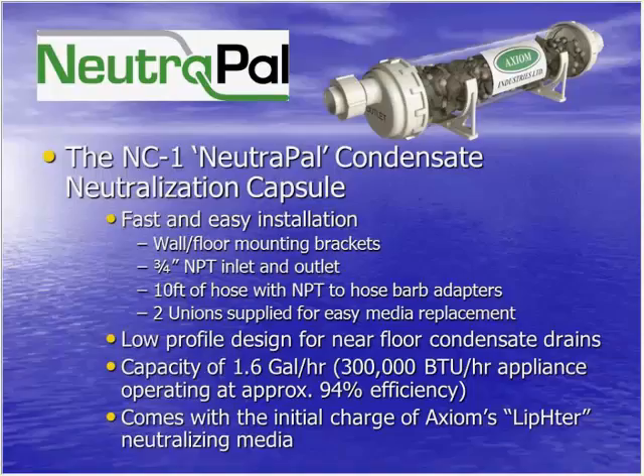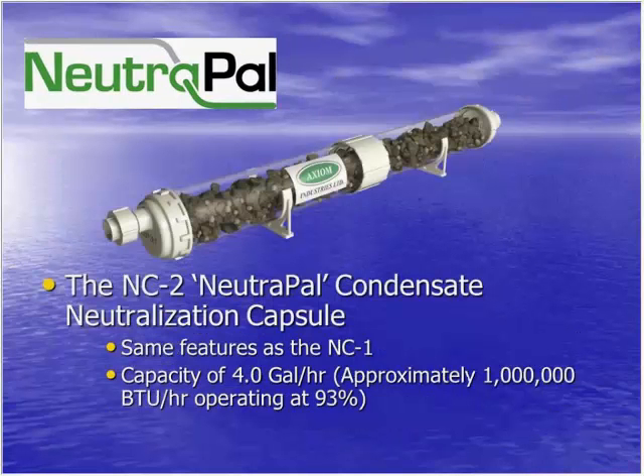This is our NC2 NeutraPal. All the same features as the NC1, obviously just an increased capacity because it's lengthened. And this one's 4 gallons per hour, which is approximately a million BTU per hour application operating at about 93% efficiency.